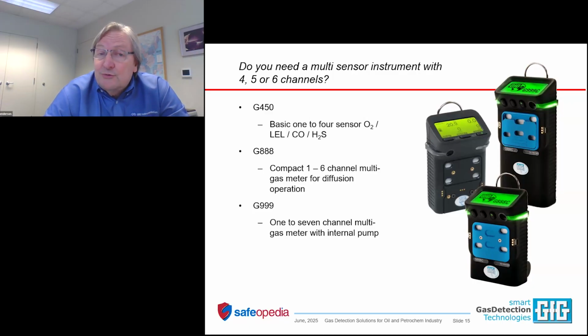The backbone of oil industry instruments continues to be a four-gas instrument like the one that you see here, which is one of our own products. It's a GFG G450, where you have oxygen, CO, H2S, LEL, and that's it. It's simple to use. Sometimes you need more than that, as we've discussed. The G888 has the ability to measure a couple more hazards. So you could add carbon dioxide and SO2, or carbon dioxide and NO2, but we have a lot more opportunities for measurement of additional analytes or gases.